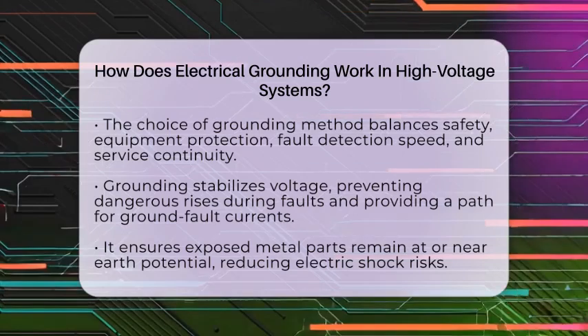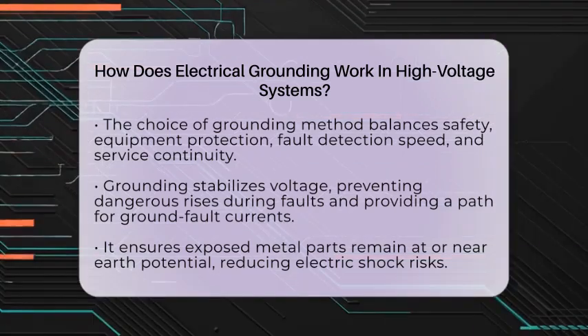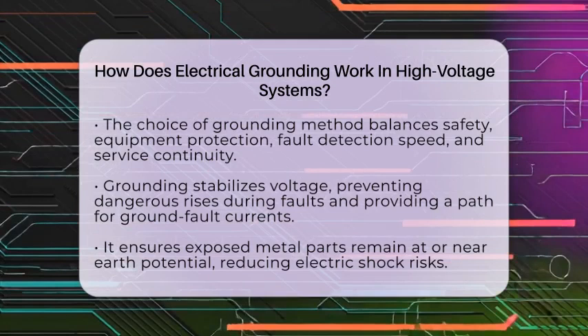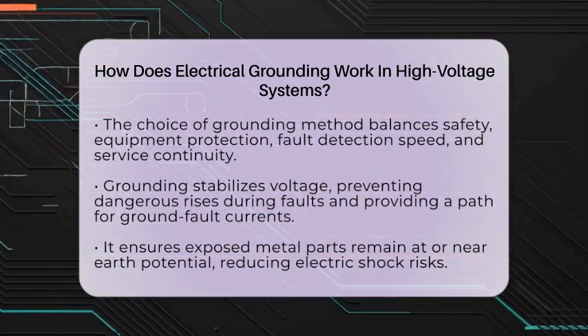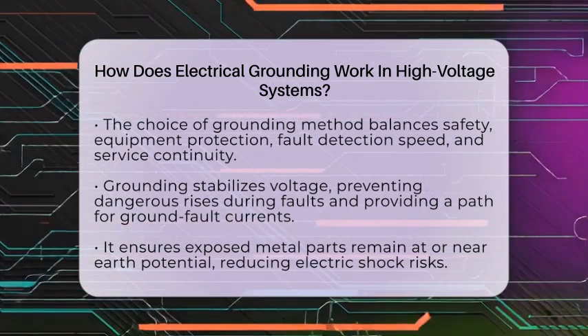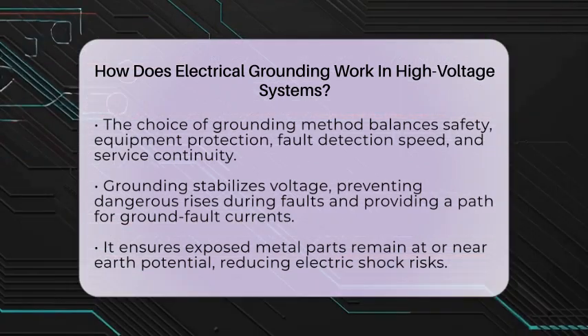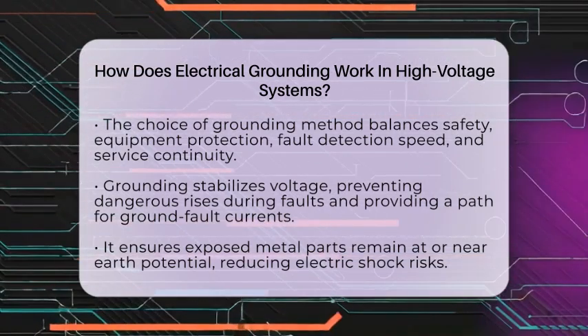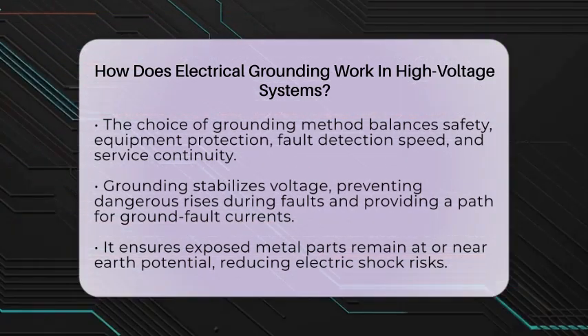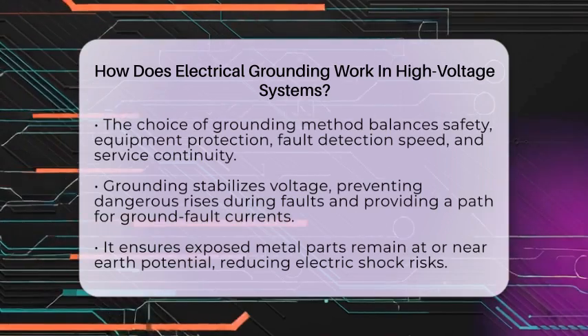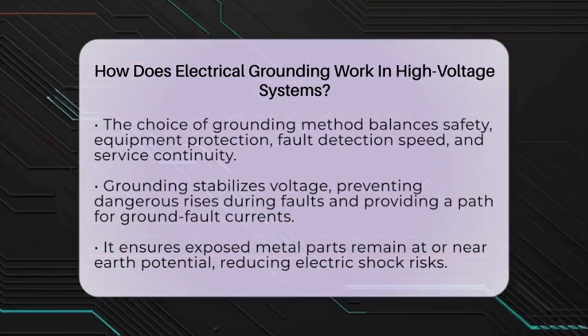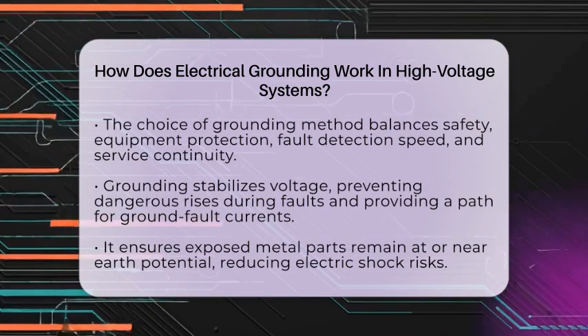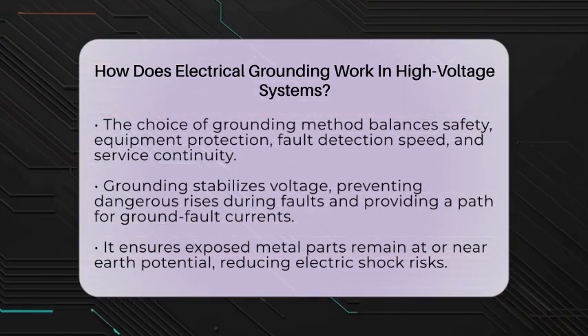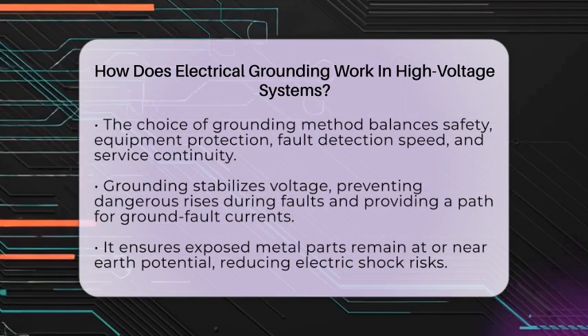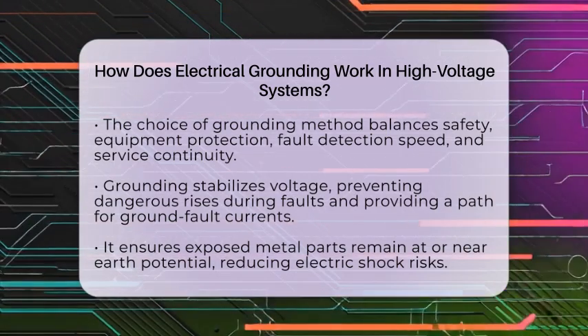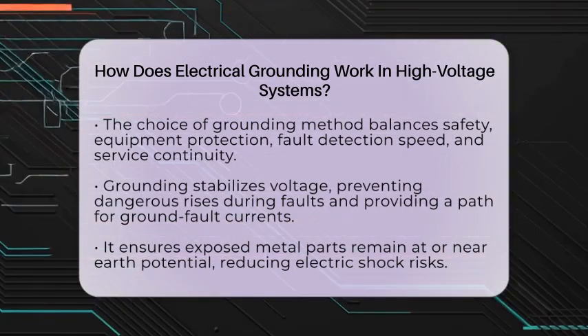Grounding serves several key functions in high-voltage systems. It stabilizes voltage by connecting the neutral point to the earth, preventing dangerous voltage rises during faults. Grounding also provides a direct path for ground fault currents to flow back to the source. This allows protective relays and circuit breakers to detect faults and disconnect the affected section quickly. Additionally, grounding limits the voltage on equipment insulation during faults, which helps prevent insulation breakdown and equipment damage.